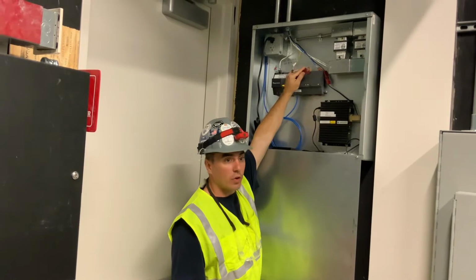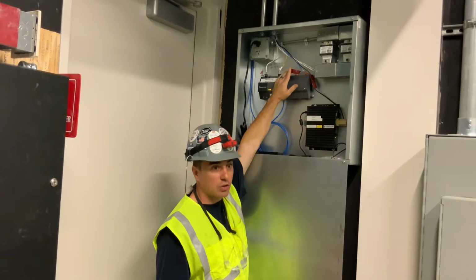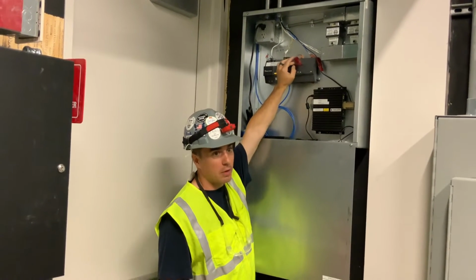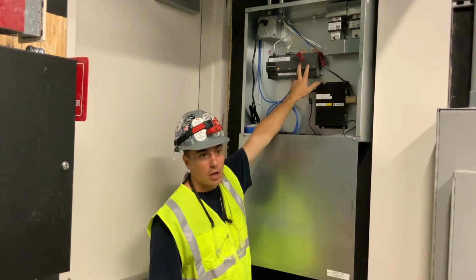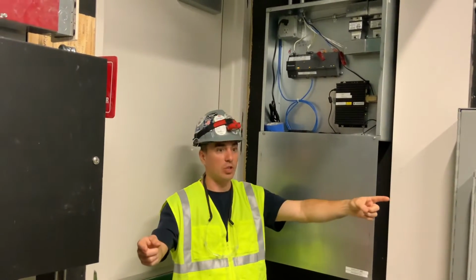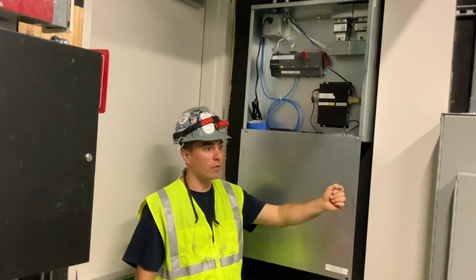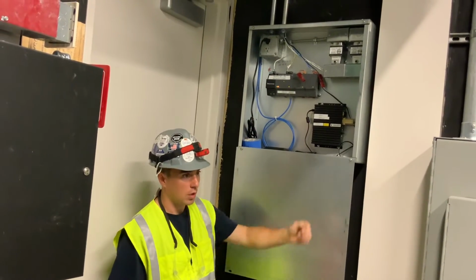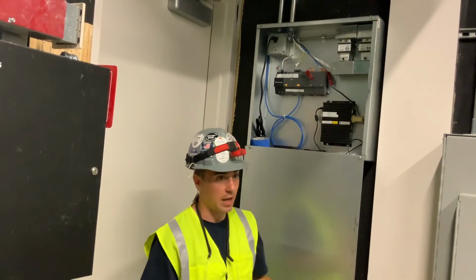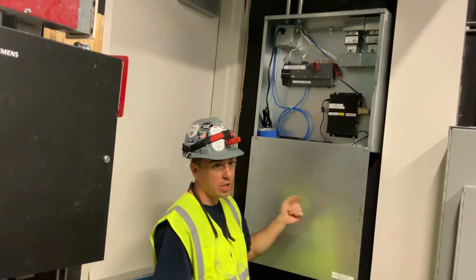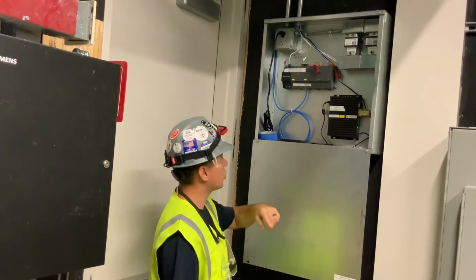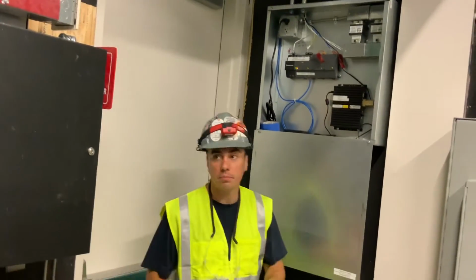The red things that you see on the line communication are end of line resistors. So there's only going to be 4 of those in the building. You have 2 here, and then there's 2, one on the end for each of the lines. So most of the valves you go to won't have those. So if you see that, that's why it is. Anything else you go to, all of the line communication is daisy chain. So most things you go to, you'll have a blue in and a blue out.